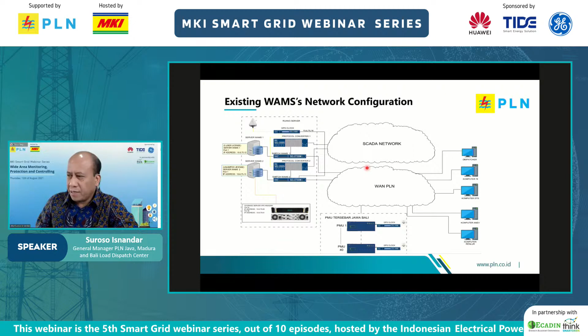What we have at the moment is the configuration of the existing WAMPAC network, where PMUs are connected and scattered across substations. At the moment we have 38 locations, and we are also trying to utilize the PMU function from the DFR, or disturbance fault recorder, of which we have around 120 or more, so we are talking about 160 points total. These are then connected through the PLN wide area network, separated from our SCADA network, in a configuration with cyber security.